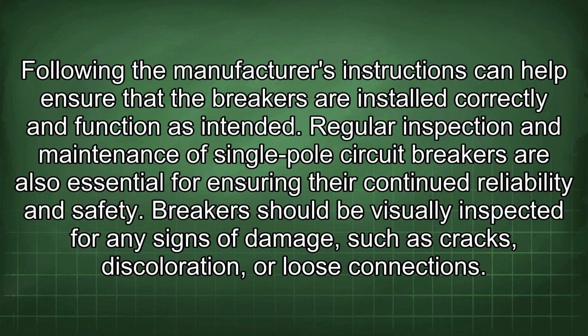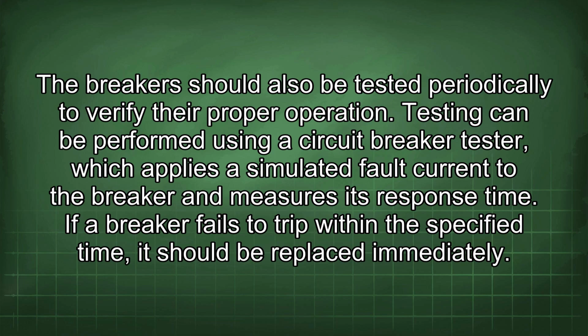Regular inspection and maintenance of single-pole circuit breakers are also essential for ensuring their continued reliability and safety. Breakers should be visually inspected for any signs of damage, such as cracks, discoloration, or loose connections. The breakers should also be tested periodically to verify their proper operation. Testing can be performed using a circuit breaker tester, which applies a simulated fault current to the breaker and measures its response time. If a breaker fails to trip within the specified time, it should be replaced immediately.